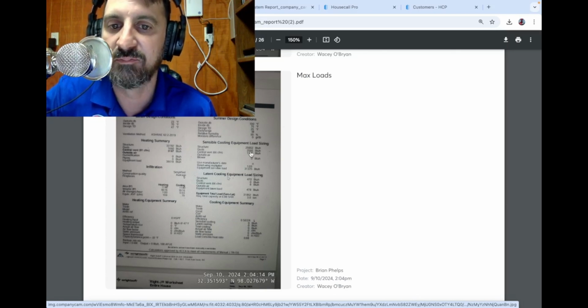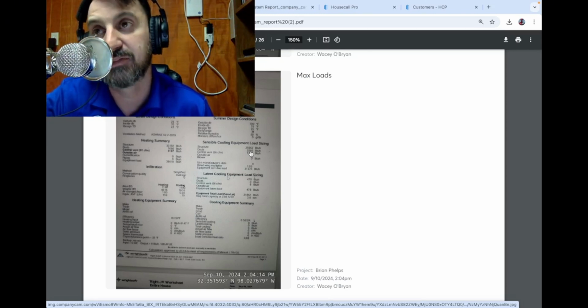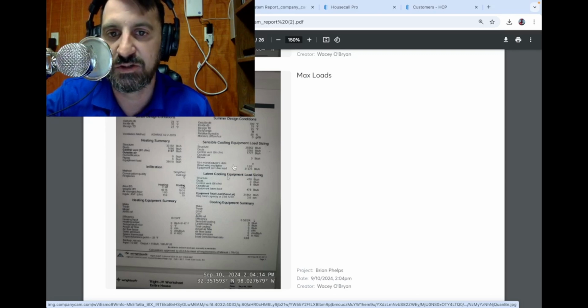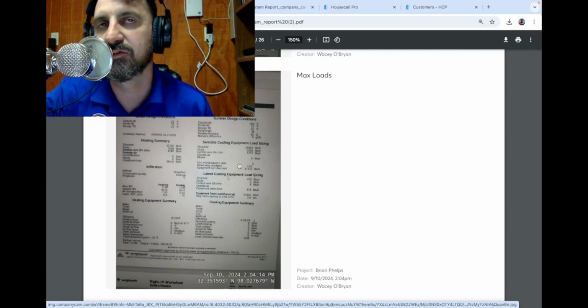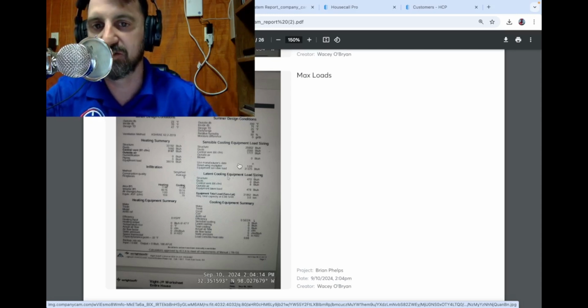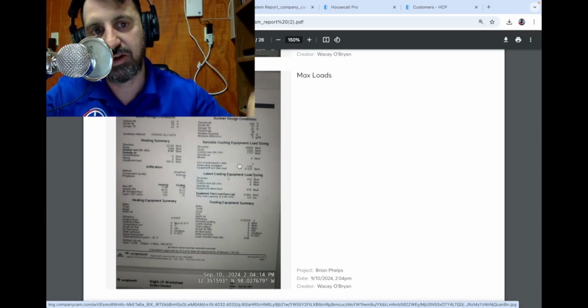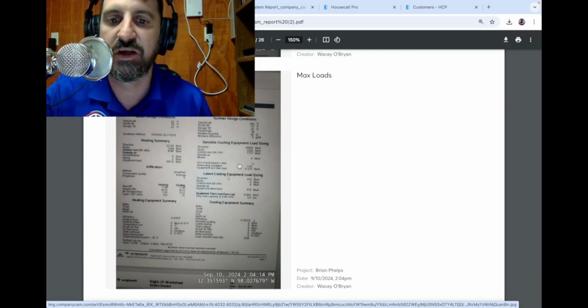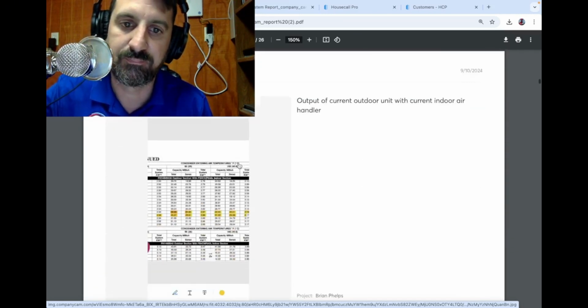Remember, this is the hottest day of the year that it needs this 31,375. That means that the rest of the time you drop to 95, you drop to 90, you drop to 80. It does not need near this much. It's not a straight line going down. There's compounding factors as you go down. So when you're at 80 degrees, it isn't an, hey, we go from 100 to 90, we can just drop the size 10%, 20%. It's a compounding thing, and your load at 80 degrees versus 100 degrees is much less than 20% less. So keep that in mind.